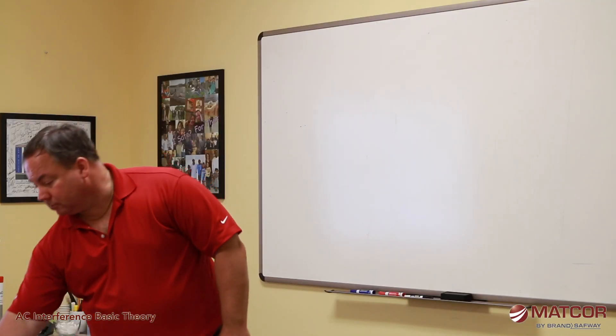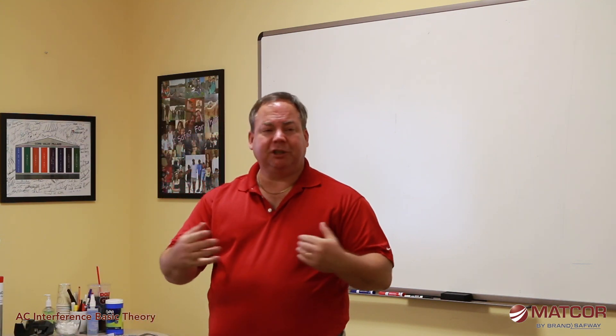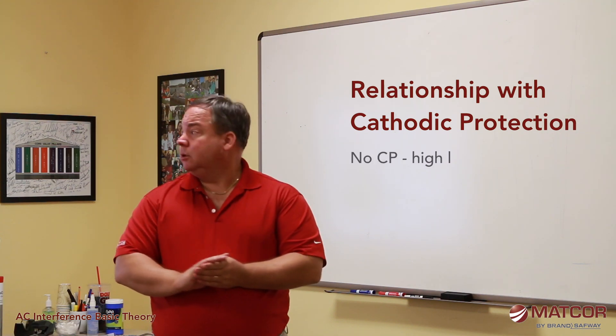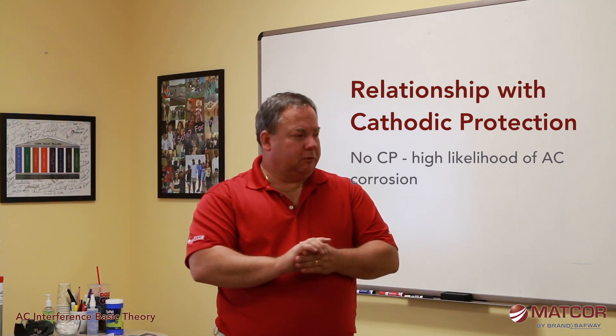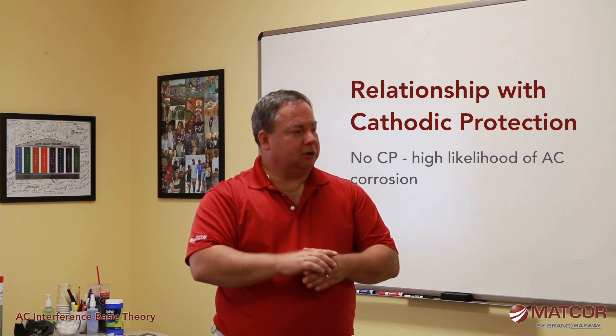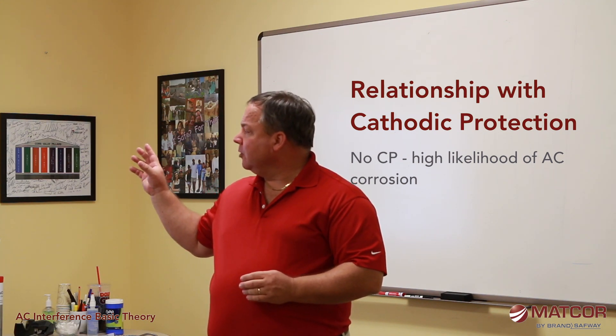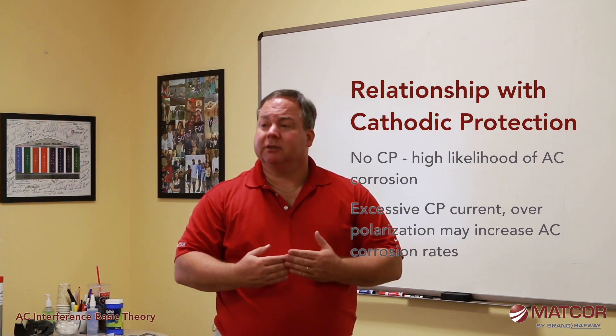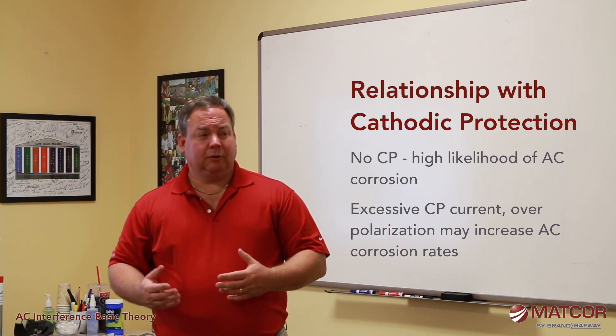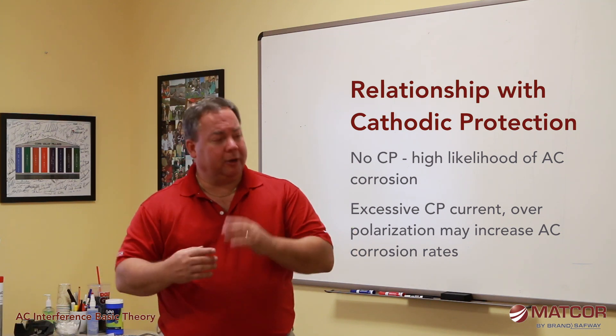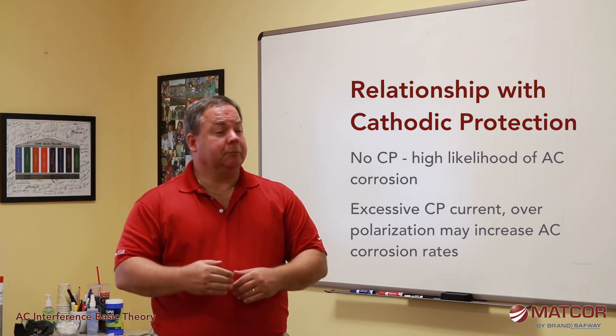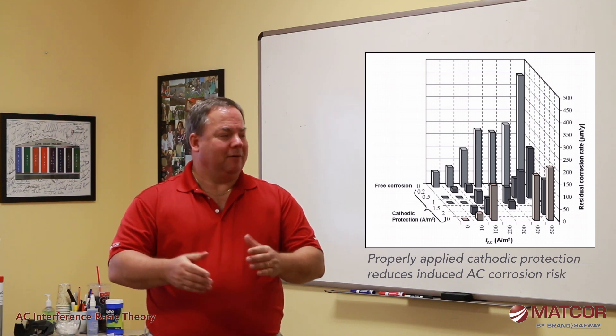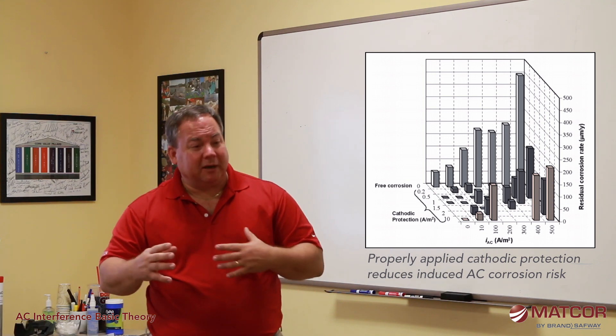Recent studies have shown a relationship between AC induced corrosion and cathodic protection. If you have no cathodic protection, your AC induced corrosion rates are purely a function of how much AC is being discharged. However, excessive CP current can actually exacerbate the AC corrosion process. So if you're in an area with high voltage lines, AC being picked up on your pipeline, and low resistance environments, you want to be careful not to put too much CP on your pipeline. They're still working out exactly what those mechanisms are, but this is what's been observed in recent testing.